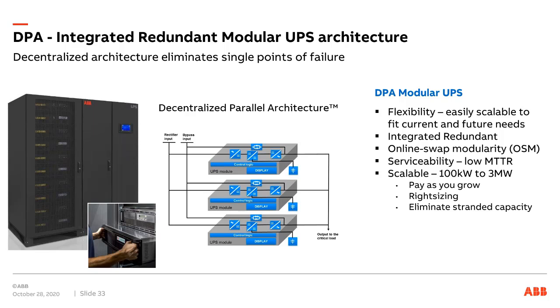And tying back, as I mentioned, even all monolithic UPSs are actually modular in design, even when they don't operate like that electrically. Even if today you were to build a monolithic UPS with a 1 megawatt rated inverter, it would still have parallel IGBTs in there. So whether it's smaller modules, each with their own set of IGBTs that operate in parallel, or a bigger one, electrically it doesn't make a big difference.